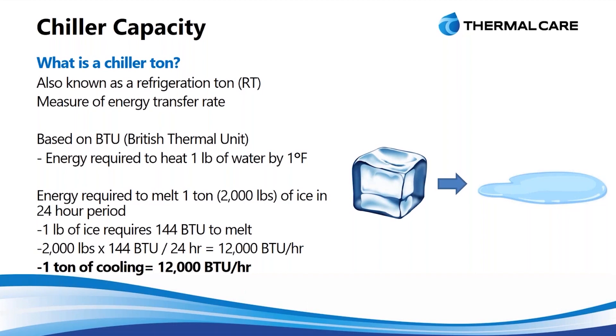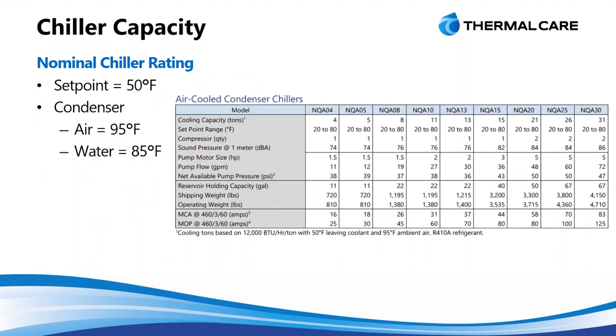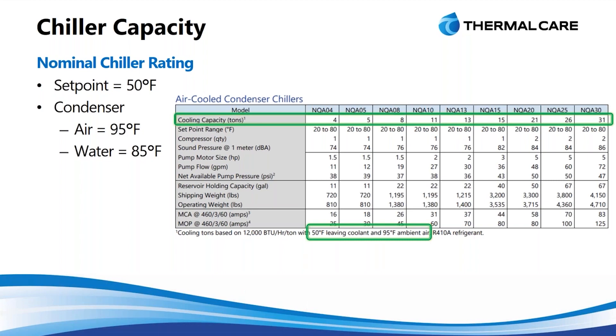I bring up chiller ton because we're going to start talking about the ratings of chillers, since that's really where the major selection point of a unit is — does it have the capacity to provide enough cooling for your process? What I have shown here is a typical spec sheet chart from a Thermal Care spec sheet for our NQ series chillers. In it, we can see the cooling capacity is denoted in tons. If you see that superscript, it leads to a footnote pointing out the conditions used to rate these chillers. We call that a nominal chiller rating.